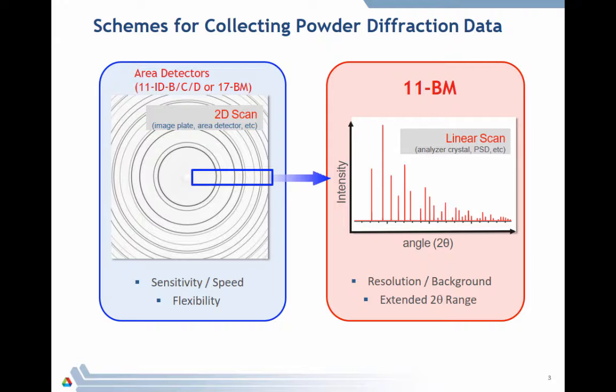On these point detectors we'll have here, you have better resolution, better background. Very often you'll have extended 2θ range, but your data collection times are very much longer. Even at the quickest we can measure at 11-BM, we're talking about the order of minutes, and a standard scan, an hour or more if you want something really unique.